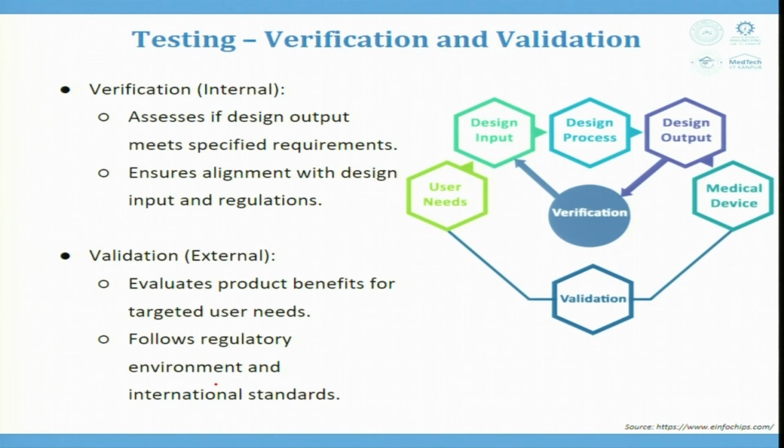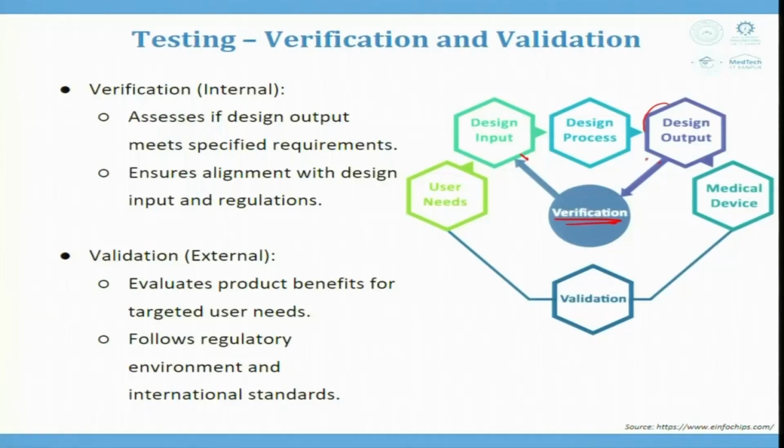As it is mentioned before as well, there is another schematic that tells that verification is between the design input and design output. Design output is whatever we have got. For instance, if I have designed a medical device, maybe a smart watch, the size of the watch, the performance of the watch with respect to the input given, and whether it is giving the right output, the heartbeat is being noted, the pulse is being noted properly or not. This is design output that is verified with the design input.